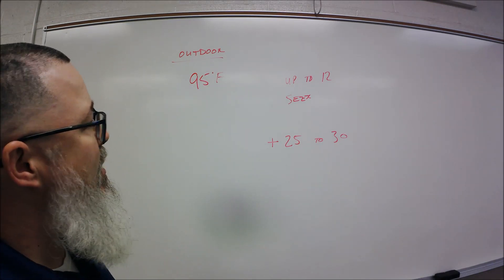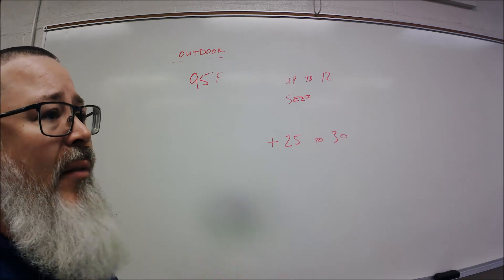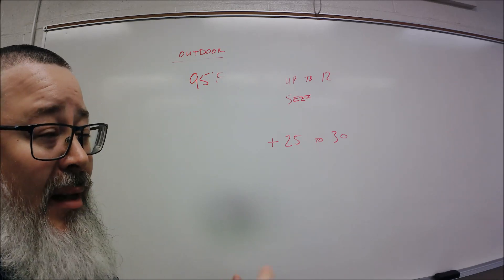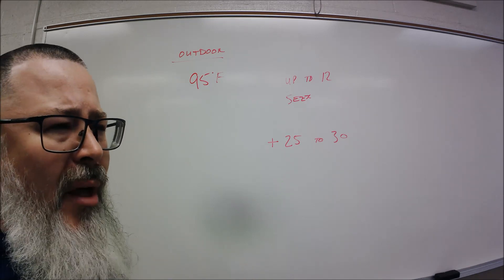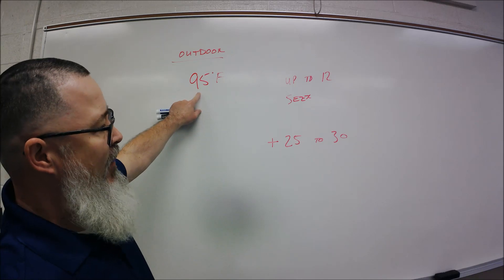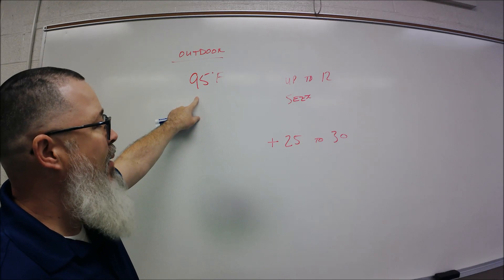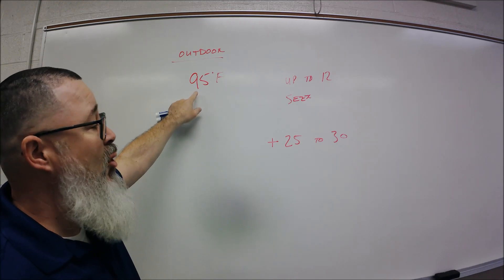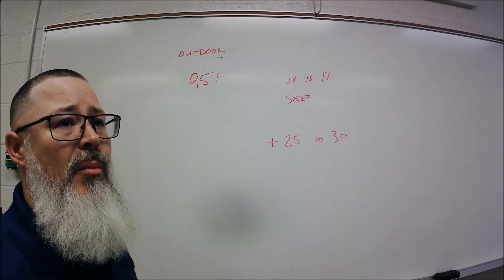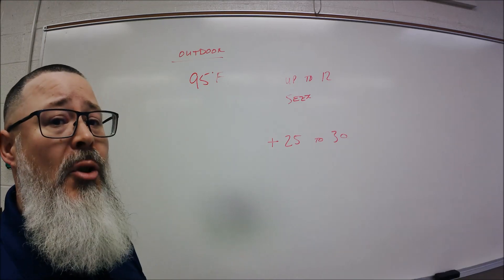So if it's 95 degrees and I have a 10 or 12 SEER unit, I'm going to add 25 to 30 degrees above that ambient. I like to work with a range so I'm not nailed down looking for one number. If I add 25 to 30 degrees, my condenser saturation temperature should be somewhere between 120 and 125 degrees. That's the saturation point on my condenser.